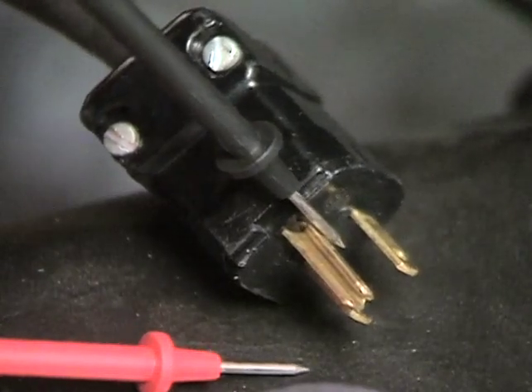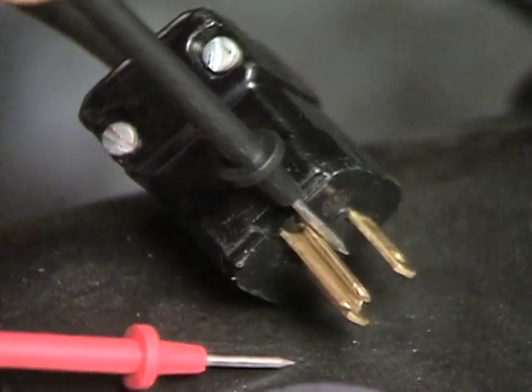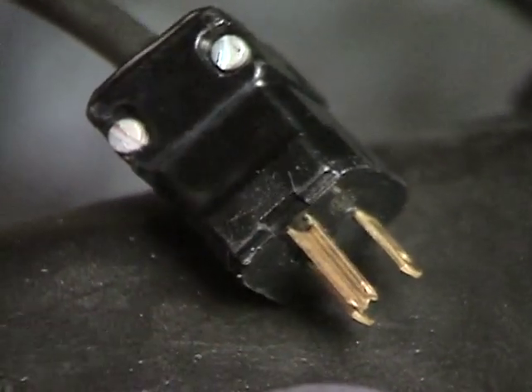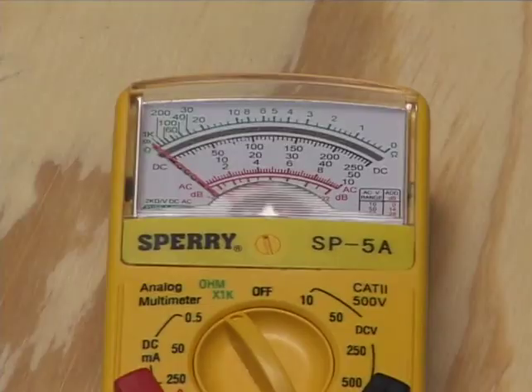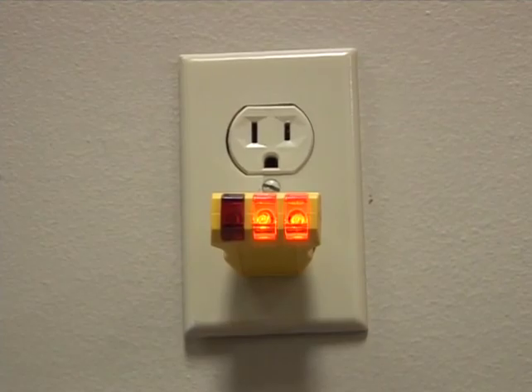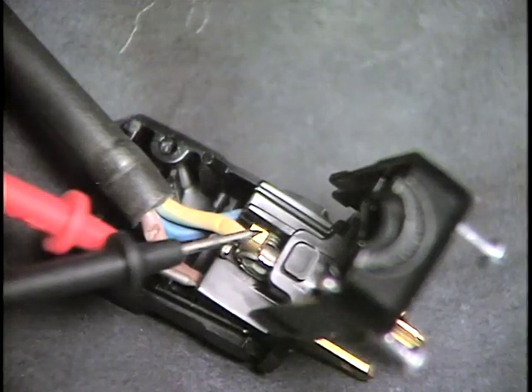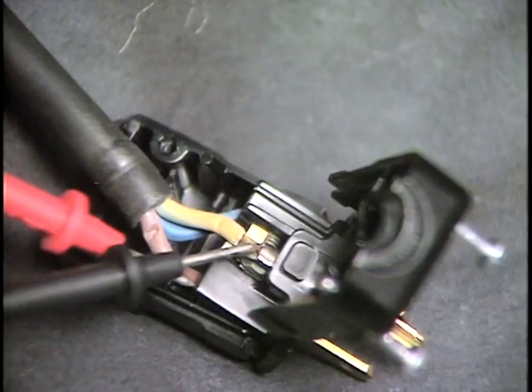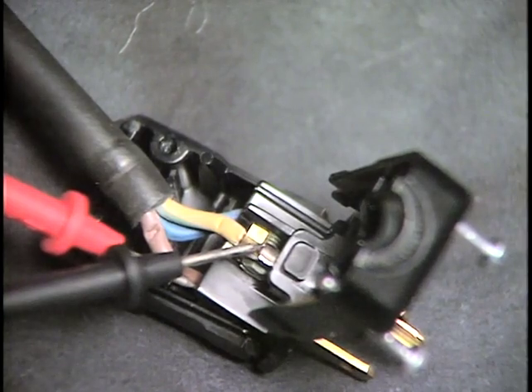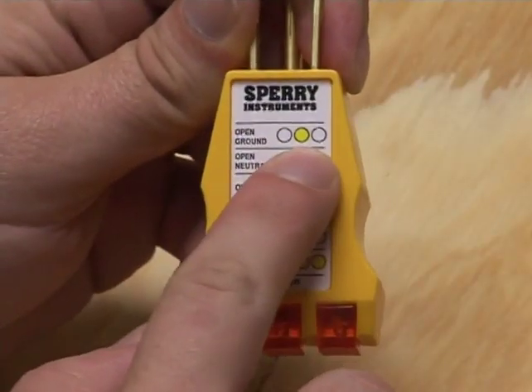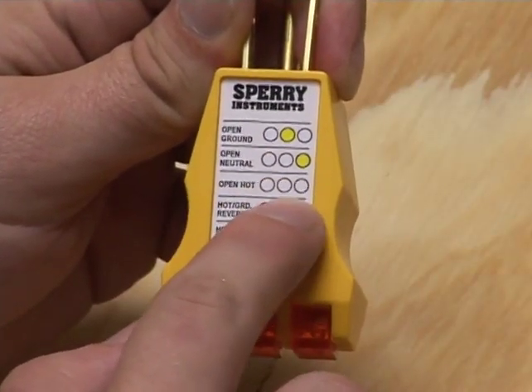To perform a continuity test, ensure that the equipment grounding conductor is electrically continuous. This test can be performed with a simple continuity tester, such as an ohm meter or a receptacle tester. The terminal connection test ensures that the equipment grounding conductor is connected to its proper terminal. This test can also be performed with a continuity tester.